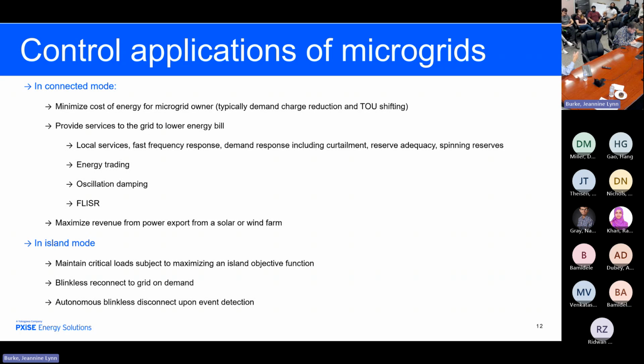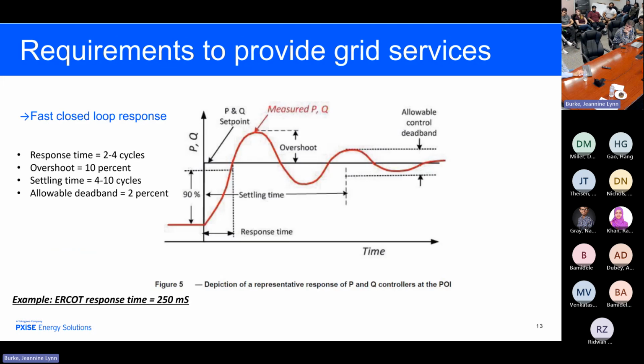That's another issue that you'll see in the literature. For example, Duke Power recently released a brand new, top of the state-of-the-art microgrid controller. It only takes 30 seconds to black start to reconnect. Okay, that's really not in the definition of microgrids from the IEEE. You need to be able to seamlessly connect, seamlessly disconnect. Now, I'll explain one way to do that.